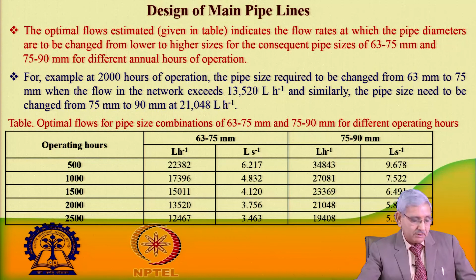So, design of main pipeline: this was the optimal flow criteria, and now we are taking velocity as the criteria. The limiting velocity is taken as 1.5 meter per second as per the recommendation of ASAE. So, flow velocity in the main pipeline for different flow rates: when we are considering 63 millimeter pipe size, we find the area of this pipeline, and then with different expected flow rates, we get different velocities for the different sizes of pipeline.